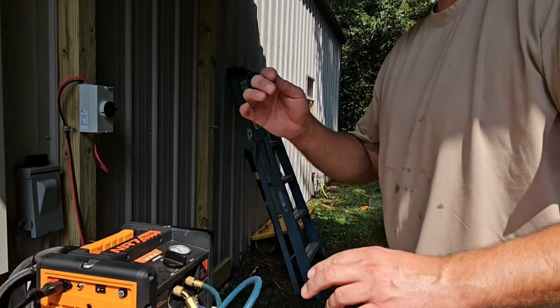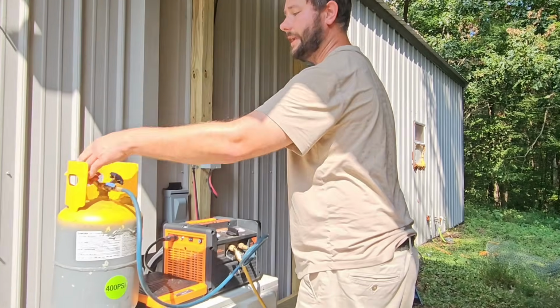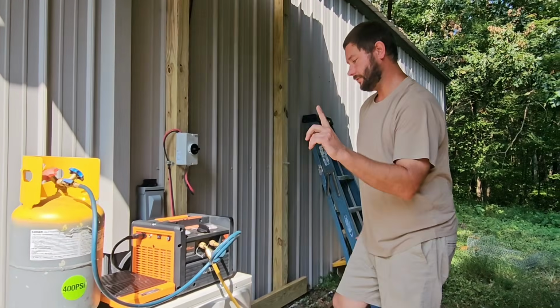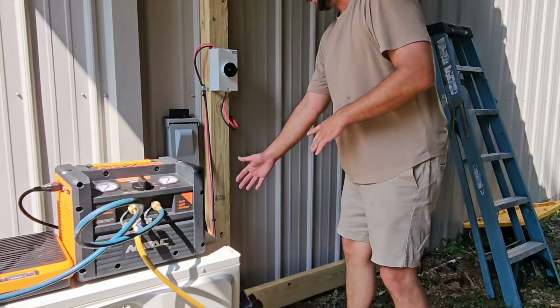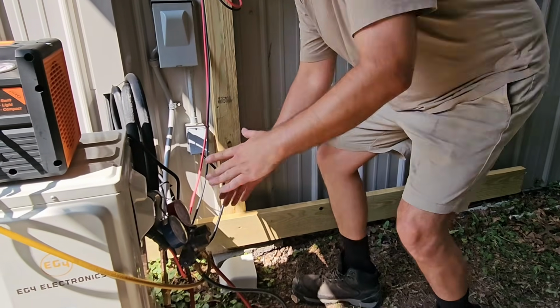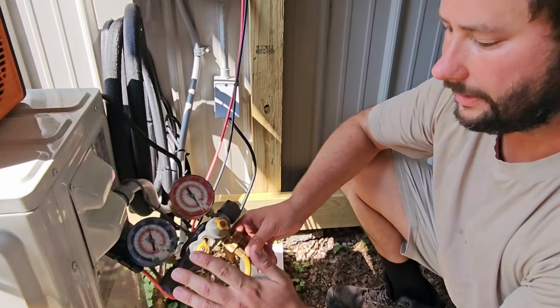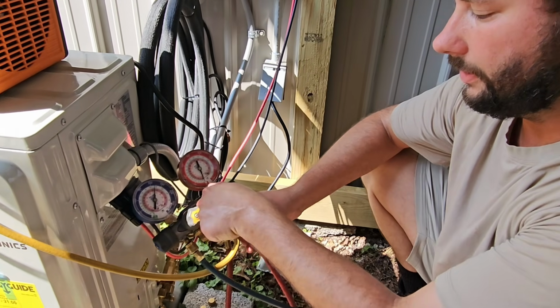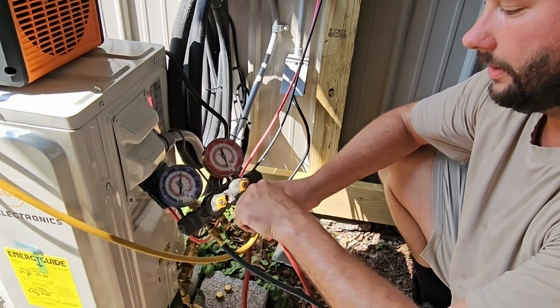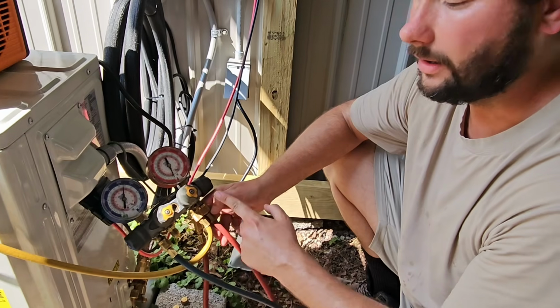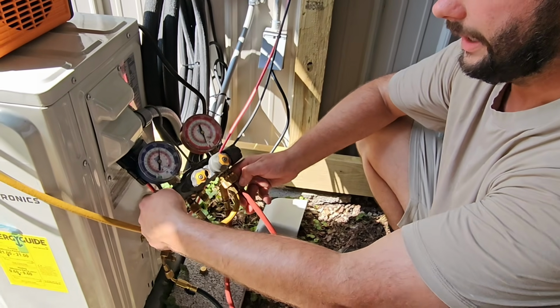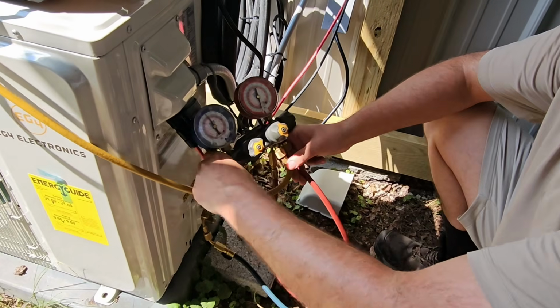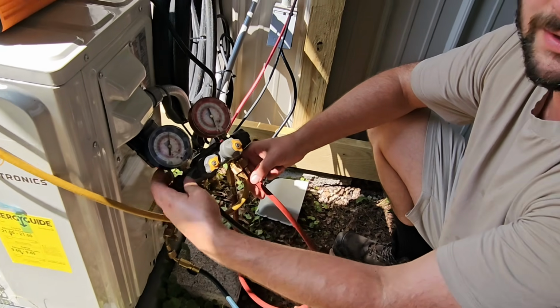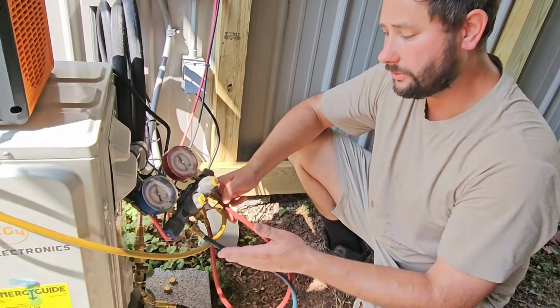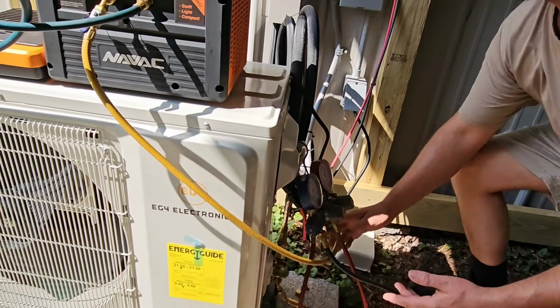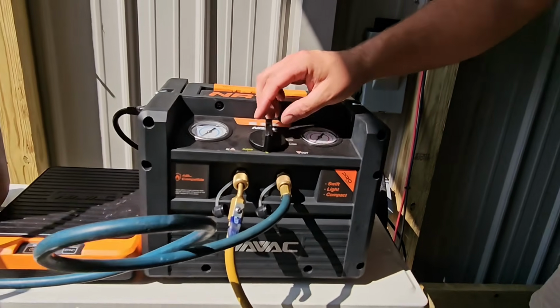Now, what I like to do is keep my recovery tank closed. Then make sure I've got power on my recovery machine. I've got power. And then to start recovering that refrigerant, we're going to open our yellow valve on our manifold gauge, and then our blue. This is going to allow the refrigerant to exit the mini split, run through the blue side of the gauge, exit through the yellow, and into our recovery tank.